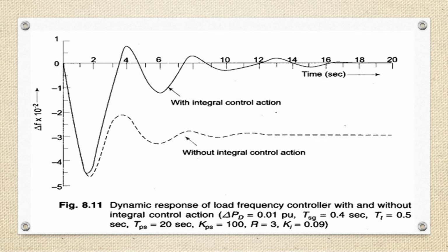This integral will be the time error of a synchronous electric clock run from the power supply. Modern power systems track this integrated time error all the time, and corrective action will be taken by a large station in that area as soon as the time error exceeds some prescribed value. If the error exceeds that value, immediate action will be taken.